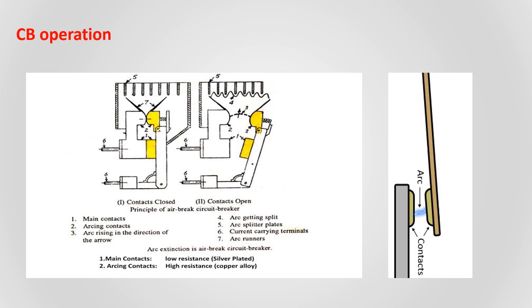The arc travels through the arc runner and is extinguished in the arc splitter. For better understanding, you will see this video to know how it is extinguished. In real time, it takes less than three milliseconds for short circuit and make or break operation.